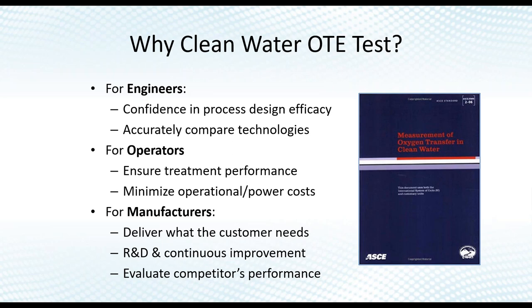Getting independent data is important. From an operator standpoint, they obviously want to make sure their facility works. If their effluent BOD is 47 and they need 30, it's their responsibility — they're the ones signing the DMRs. Operators are also interested in operating costs. OTE testing measures both how efficiently oxygen transfers from bubble to water and how efficient the device that produces the bubbles is — which determines energy costs and operating expenses.